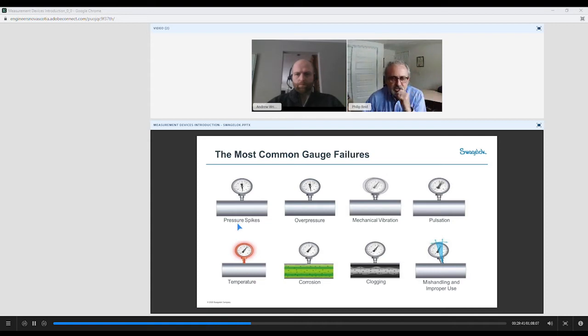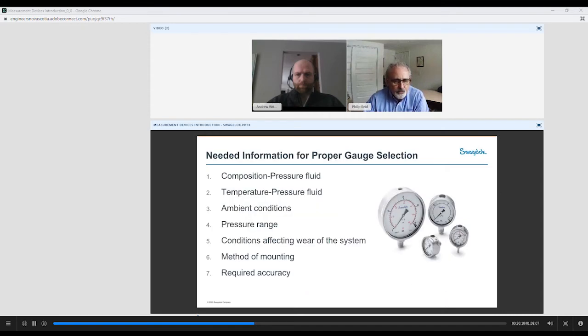We can tell as soon as we take the back off that gauge if it's experienced a pressure spike. There are many indicators. And the same with overpressure, very common. Mechanical vibration, where the gauge is moving around, has an adverse effect on the internals of that gauge. Pulsation, back and forth, again, you can imagine what that's doing to the gauge. Temperature can affect the gauge. Corrosion, clogging media, and mishandling and improper use as well can be an issue.